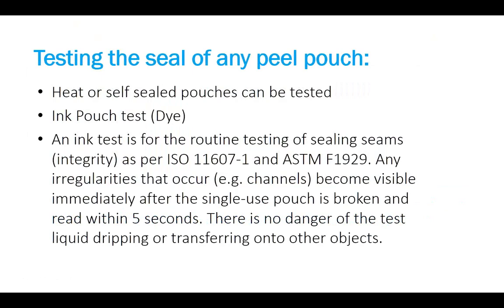So, testing the seal for any type of pouch. Heat or self-seal pouches can be tested. It's called the ink pouch test or dye test. And this test is a routine testing of sealing seams integrity per ISO 11607 and ASTM F1929. Any irregularities that occur, such as channels, become visible immediately after this single pouch is broken, and you read within 5 seconds. There is no danger of the test dripping liquid or transferring onto other objects.